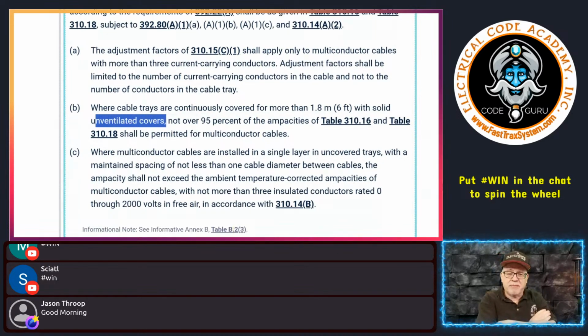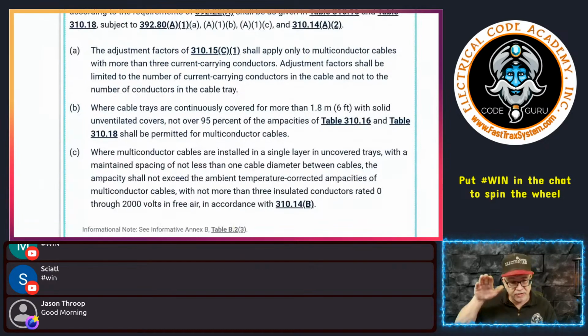Well, you may have something like this where you have a cable tray that is rated, let's say, for a hazardous location. You may have a situation like this where it's rated for outdoor use and it doesn't have any openings in it. Again, there are many different types of trays. But if you do have a cable tray with an unventilated cover, okay, talking about the cover because heat rises, then it says, okay, look, if you have this cable tray and it is continuously covered for more than 6 feet with a solid unventilated cover, okay, that's all it's talking about.